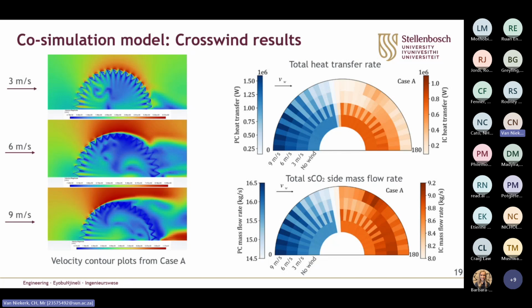And now we could take these results and then go look at what the effects are on the sCO2 side of the heat exchangers. So this is shown by the second heat map, where we plot the different sCO2 side mass flow rates to each individual tube bank situated around the tower, and just using the same concentric ring approach as the heat rejection rates. And in this case, we see that the sCO2 side mass flow rates actually track the heat rejection rate plots, and this is simply due to the tube banks rejecting more heat lowers the internal sCO2 gas temperature, which results in a higher density in these tube banks, and that causes the internal velocities to drop, and then the pressure dropping through those tube banks as well. So then what happens, the system responds by balancing the momentum across each one of these tube banks, and then directs more of the sCO2 mass into the tube banks with the higher heat transfer rates.